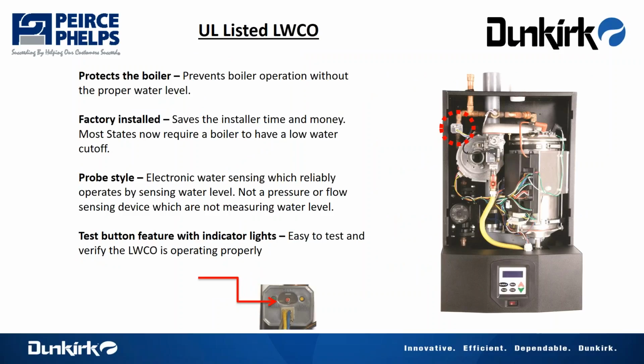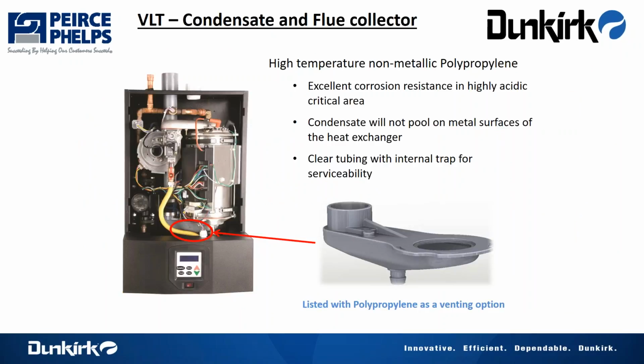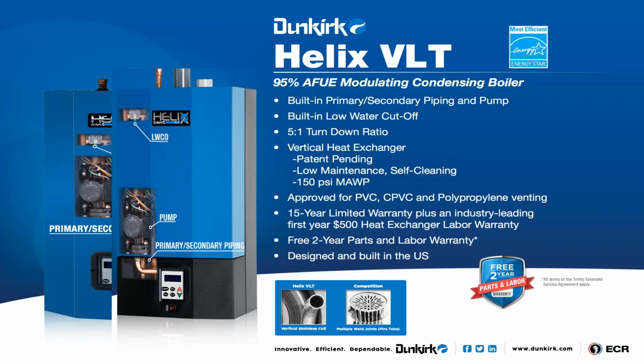The low water cutoff, probe type low water cutoff, is actually seeing the water level in the boiler. It has a test button on it for inspectors to test it. It's mounted inside the boiler near boiler piping. Condensate and flue collector sits in the bottom of the boiler, polypropylene, impervious to the acids that are contained in the condensate. A lot of condensate flue collectors on competitive models are actually stainless or aluminum, and those are not impervious to the acids. So if the condensate puddles and pools in those, you may see some pitting over time and failure. So our collector is going to last probably a lifetime of seeing condensate removal.